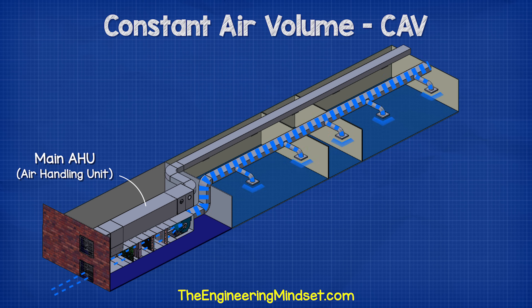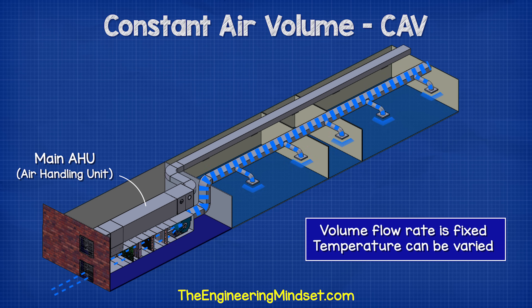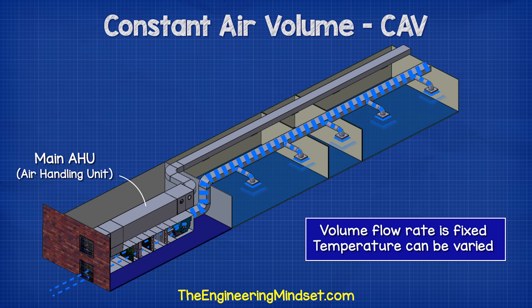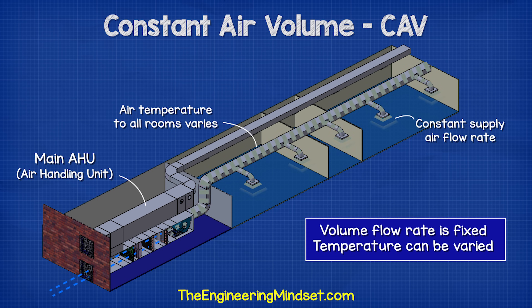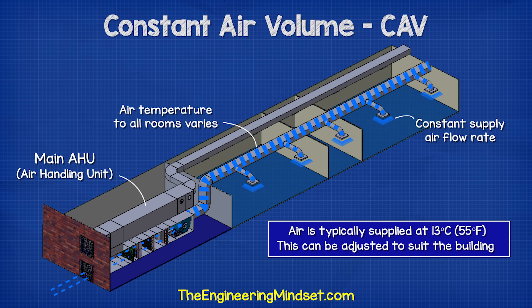CAV systems do have some limitations because their supply air temperature is varied but the volume or flow rate of air being supplied is kept constant. While the system is operating it provides air at a consistent and constant volume and only the temperature of the air changes. Typically, the air is provided at around 13 degrees Celsius or 55 degrees Fahrenheit, but this can be adjusted to suit the needs of the building.